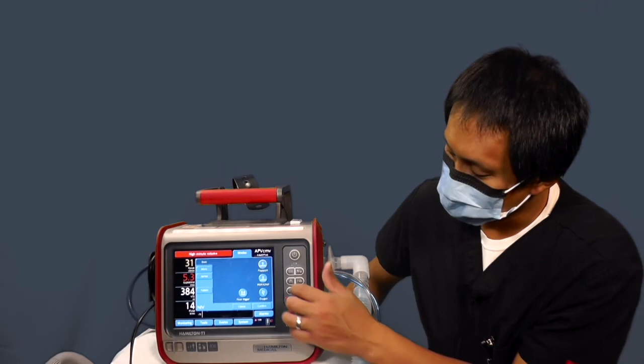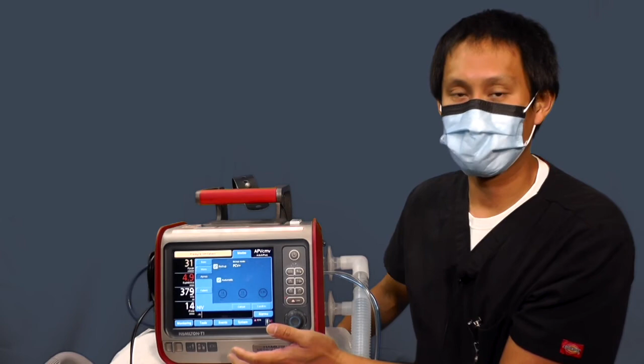One thing to note that I didn't mention in spontaneous mode is that under apnea, you do have backup and automatic. So you can actually turn the backup apnea setting off, which you should not be doing, and you can also customize the settings you want the ventilator to go to when it goes into backup apnea mode. So if you do not make any changes, it'll automatically default to what the vent thinks should be the backup setting. If you want to manually adjust, unclick that button, and then you can adjust to your desire. Okay. Currently, this is going to be in pressure control when it goes into apnea ventilation.